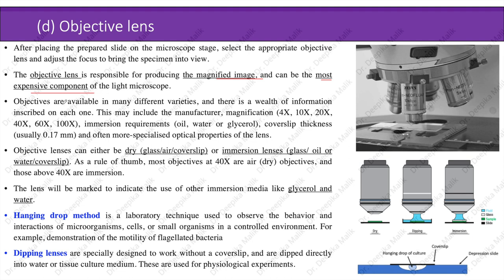Objectives are available in many varieties with information inscribed on each, including manufacturer magnification such as 4x, 10x, 20x, 40x, 60x, and 100x; immersion requirements such as oil, water, or glycerol; cover slip thickness of usually 0.17 mm; and specialized optical properties. Objective lenses can be dry — glass, air, and cover slip — or immersion lenses — glass, oil or water, and cover slip. As a rule, most objectives at 10x and 40x are air objectives, while those above 40x are immersion objectives, usually 100x.